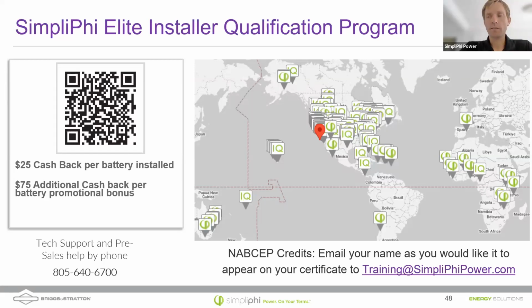Yes, that's true if the batteries go completely dead. But in most cases you can set a reserve on your batteries with a low battery cutout. So when solar is available, if you've maintained a small reserve, you can turn the system back on and have AC coupled solar producing and charging the batteries again. There are limitations with string inverters and AC coupled systems for getting that solar back, but you don't have that same issue with DC coupled solar. If your batteries go dead with DC coupled solar, the sun comes out and it's not a problem, since it doesn't need an inverter to turn on for those MPPTs to fire up and start charging the battery. So it's a good example.